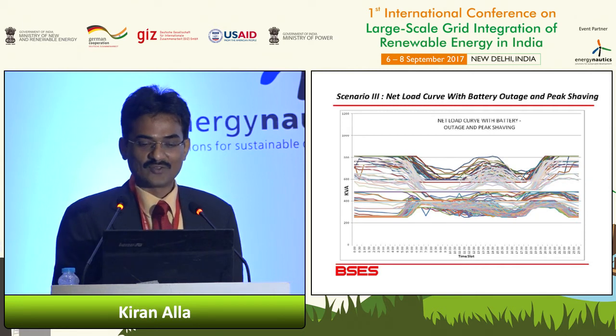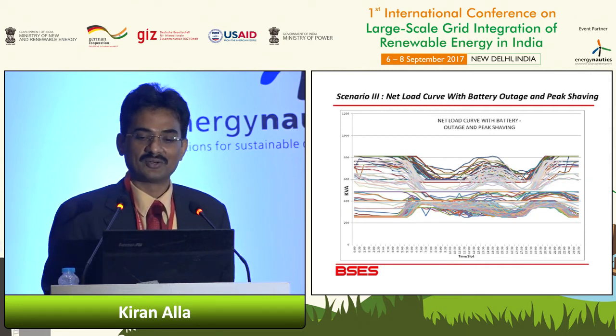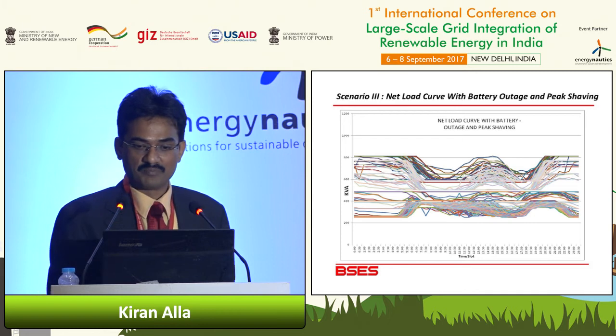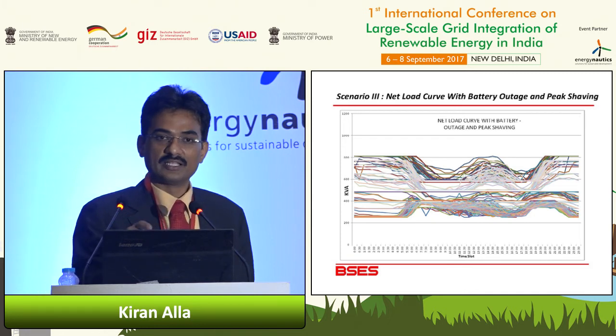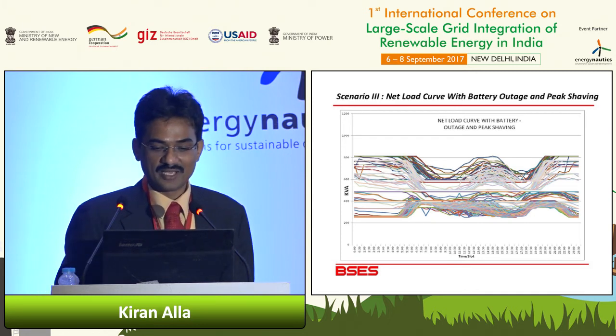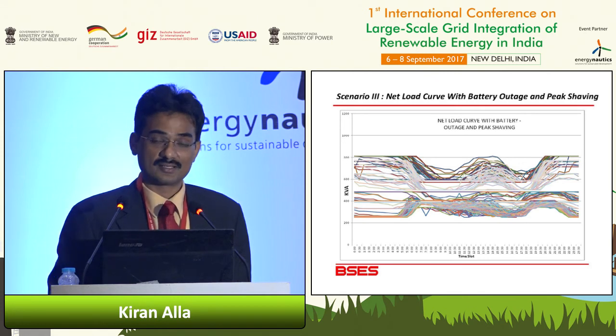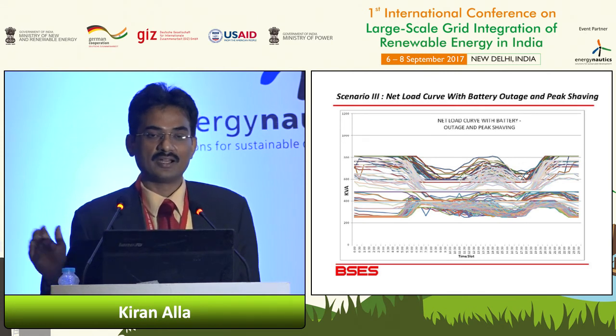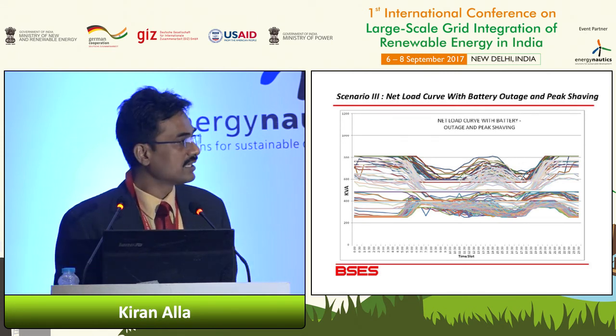Now what we try to do is look at the net load curve with battery, outage handling, and peak shaving. The outages can be eliminated using a BESS kind of system, so you can create an intended island and not see outages.